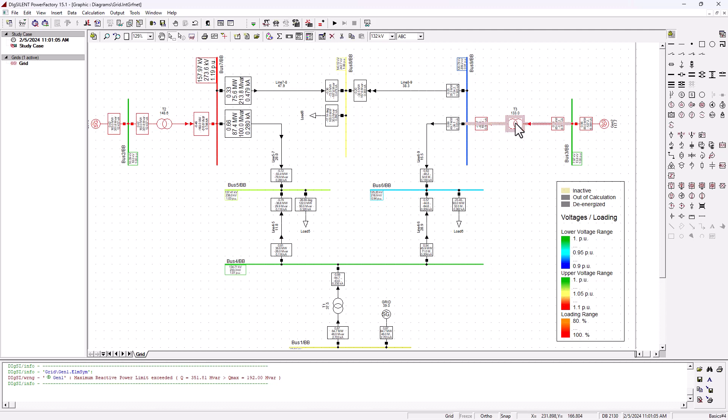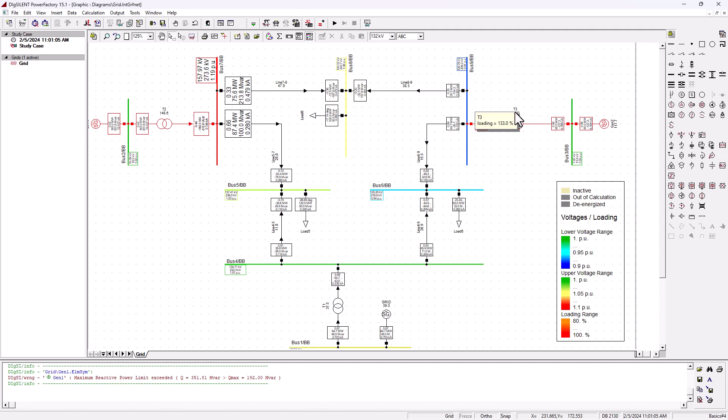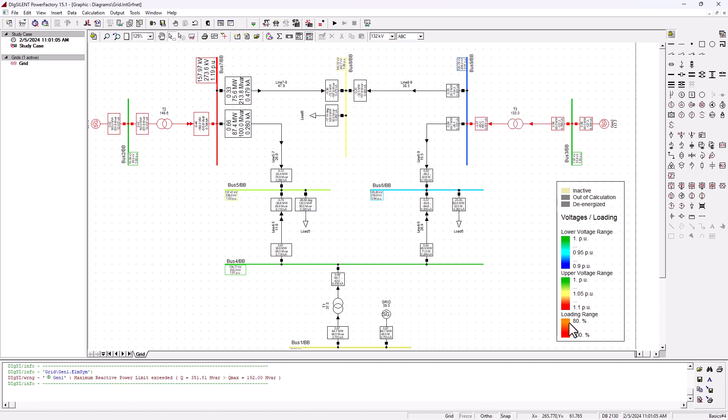For electronics and electrical components, you must avoid overloading or loading your equipment to 80 percent of its capability. Right now, we can see that this transformer here, T5, has a hundred and thirty three percent overload on it. That's a problem. We are supposed to actually accept a loading below 80 percent.